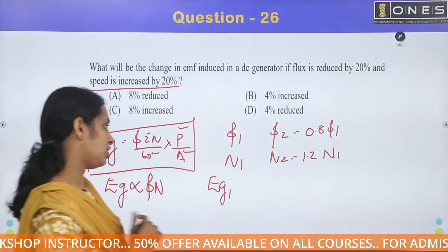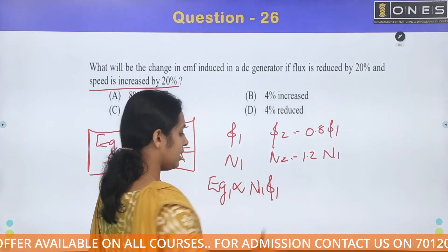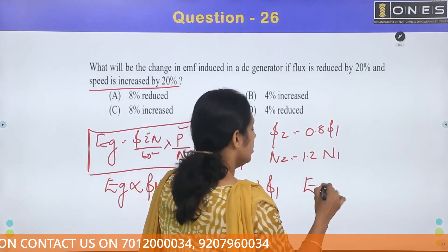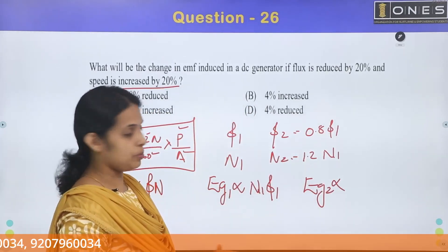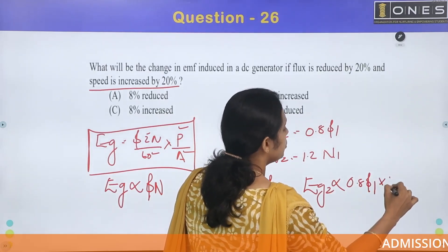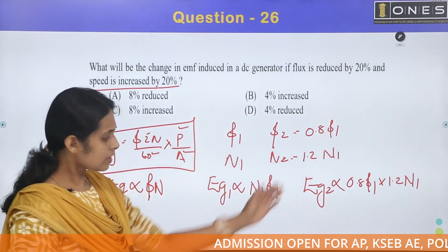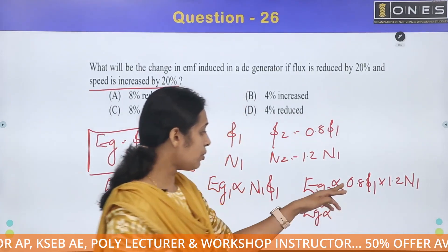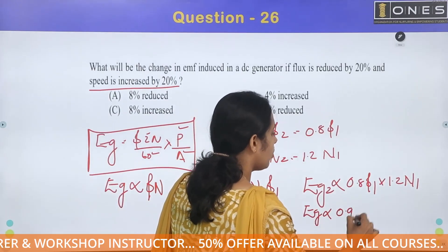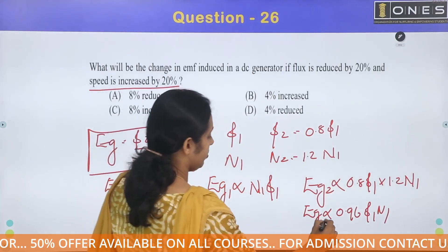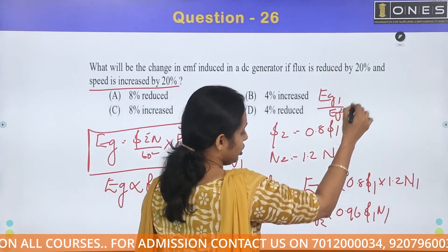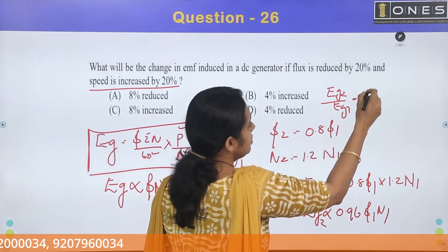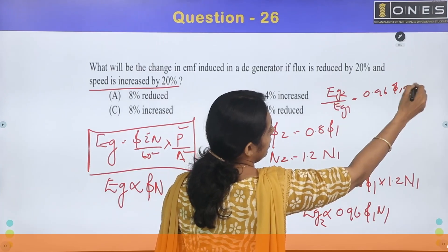Initial generated voltage EG1 is proportional to N1 × φ1. New generated voltage EG2 is proportional to new flux 0.8φ1 and new speed 1.2N1. So EG2 ∝ 0.8 × 1.2 × φ1 × N1 = 0.96 φ1N1. Therefore, EG2/EG1 = 0.96.